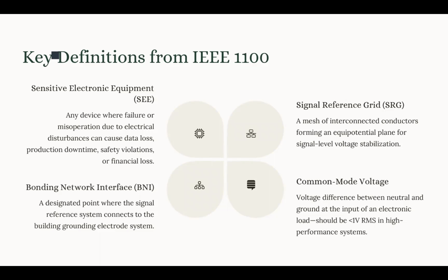This mesh, the SRG, basically equalizes the potential difference between the equipment, preventing ground loops. It also provides a low impedance return path for high frequency transient currents and stabilizes the voltage reference planes for high speed digital systems.